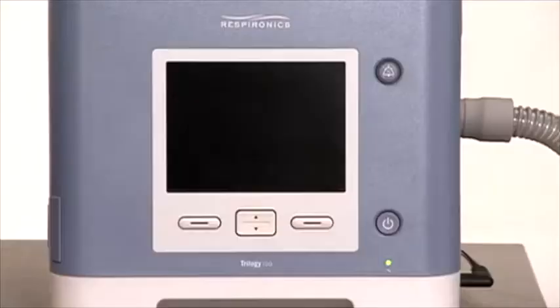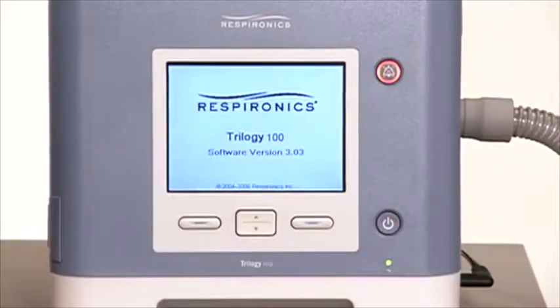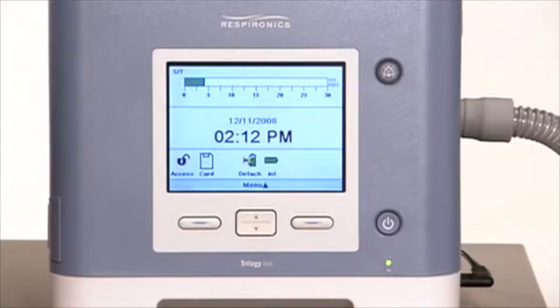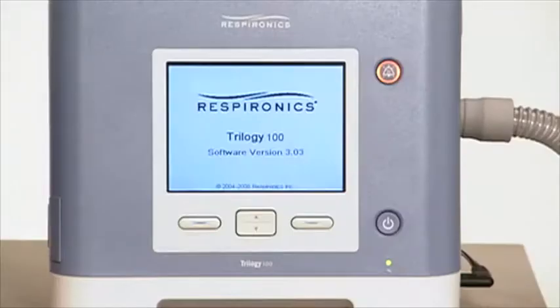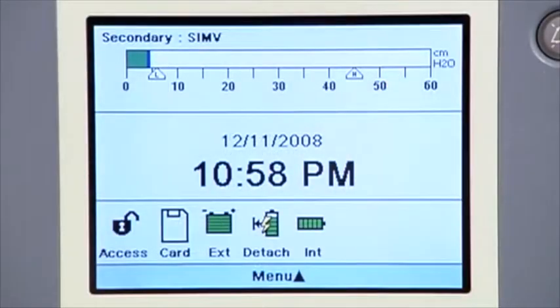To operate Trilogy 100, you must be familiar with the screen display. In this segment, we'll review some of its symbols and operations. Press the Start-Stop button on the front of the device to begin therapy. The display screen and the backlights on the buttons turn on. The red and yellow alarm LEDs turn on momentarily, and an audible indicator lets you know that therapy has started. A startup screen with Trilogy 100 and the software version appears briefly on the display screen. The ventilator returns to the most recently defined ventilator settings, and a monitor screen appears.